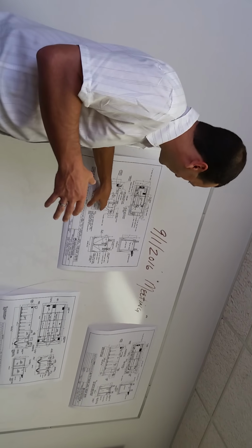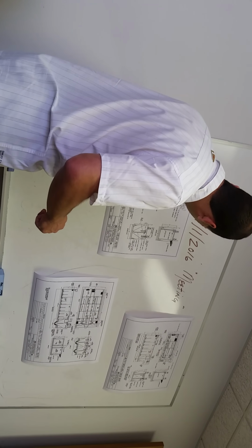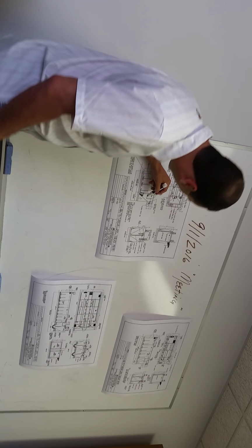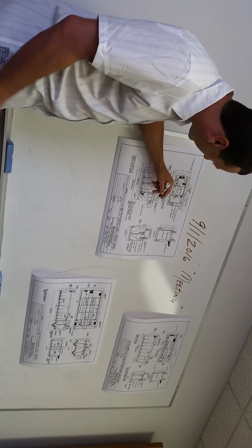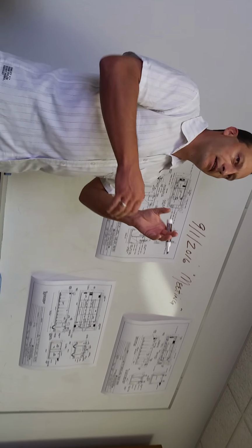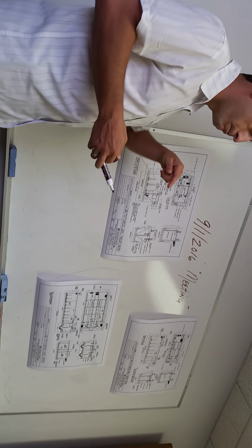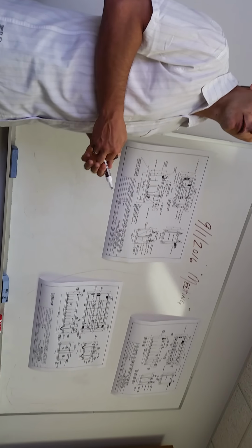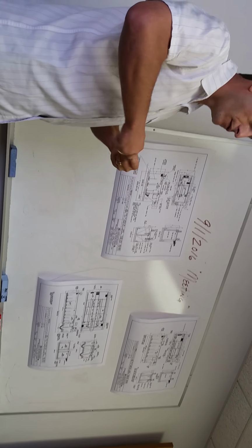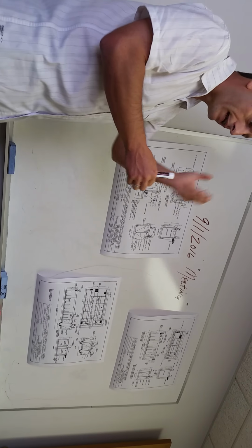And what can happen is as you get solids that start to accumulate in here, like I use brown, as you get solids down in here, as you're pulling, you might get basically a spot here where all of this stuff is here and all of this is here, but this is just going to start pulling clear water, and all of your solids have compacted, and it wormholes, or they call it all different sorts of things. But if your return starts going clear, you better scrape the clarifier, because you're not pulling any solids off the bottom. Everything's just sort of compacted, and you're just pulling out of a well.